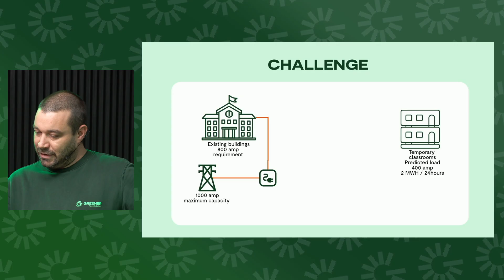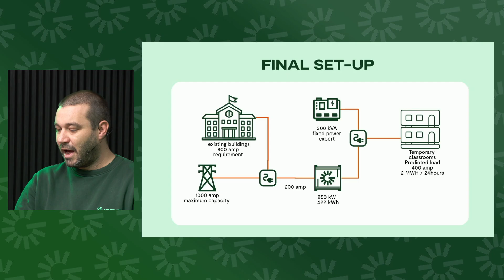So we did this quite simply, and this is one of our simple setups. This would be traditionally considered a load share setup, or one of the ones that we looked at in the past webinars. Simply, we take a 200 amp grid connection, we peak shave that connection on a battery, and then we connected a 300 kVA generator to the output side in a grid following mode that would enable us to get more energy into the battery if the load is greater than we can possibly get from the input connection.